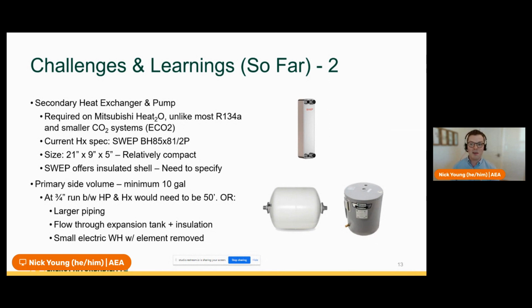It's relatively compact, and SWEP does offer an insulated shell, but you need to specify that if you want to get it. We've also learned, through Ecotope's experience on a past project, that you really need a minimum volume on the primary side of 10 gallons. With a 3/4 inch pipe run between the heat pump and the heat exchanger, you'd need about 50 feet of pipe.